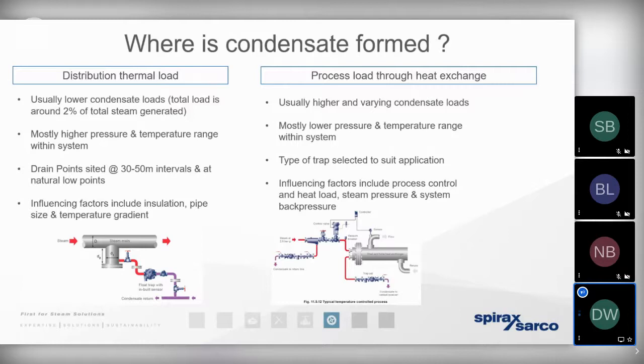We're more susceptible to steam with less energy contained within it. And we're certainly going to need to install, maintain, and inspect a greater number of steam traps. The thing to bear in mind is that 2% rule of thumb only applies when the steam infrastructure is at a nice high temperature.